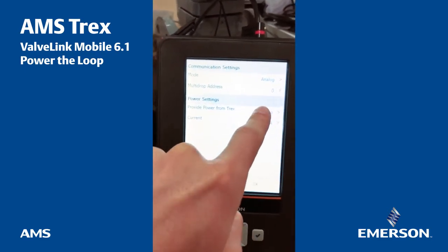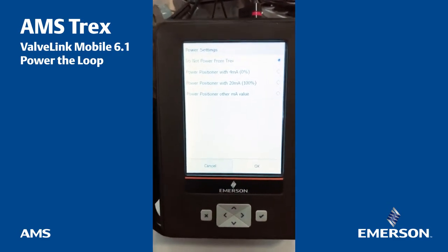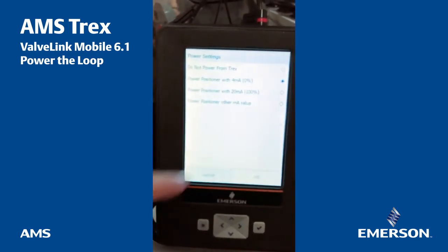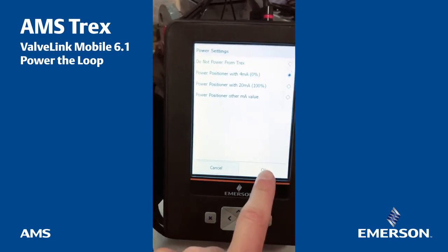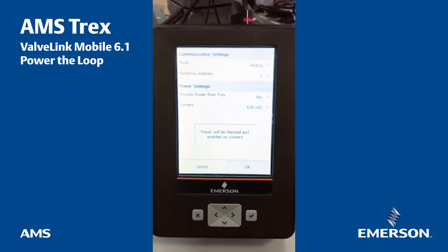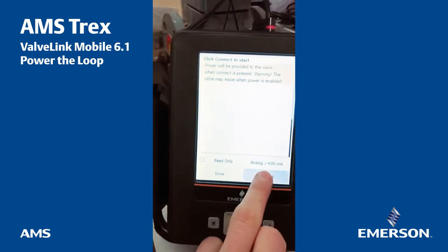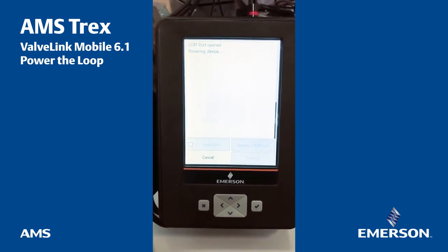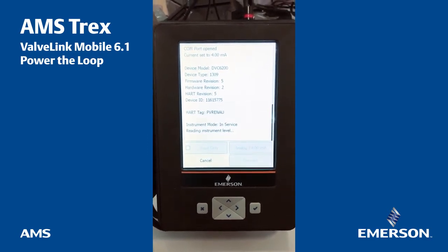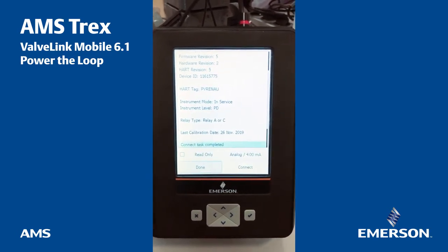Provide — yes. So I need to wait. Here I need to select the first position where I want to put my valve and with which current. The one I'm going to select is 4mA — this is where I want the valve to start with. Now I click on the button Connect. That's the first step required. It's connected to the device, it recognizes the device, gives the name, applies some power supply, and everything goes fine.